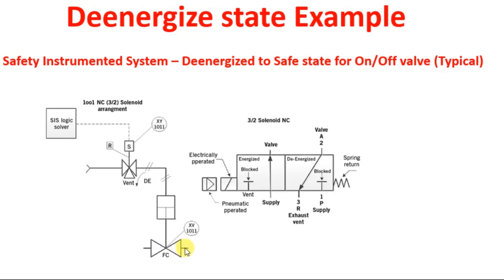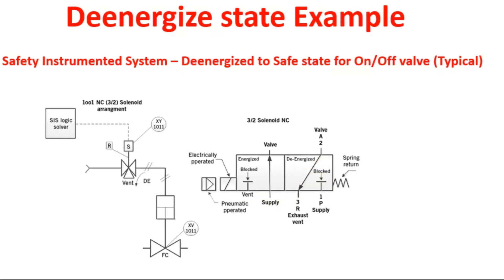This is the general working principle of a pneumatically operated actuator valve. According to the process conditions, the SIS logic solver will act and cut the power to the solenoid valve, making it move to the de-energized position. These positions are known as a spool. Internally, the spools are connected such that at one position the instrument air directly goes into the actuator body to keep it open; when power is disconnected, the spool moves internally to the exhaust port, venting the entire instrument air from the actuator body to the atmosphere to move the valve to the closed position.